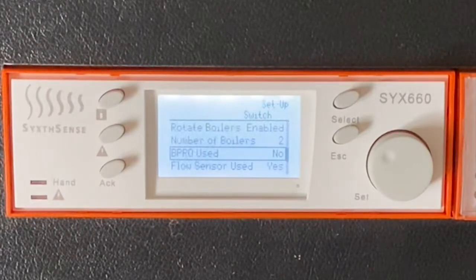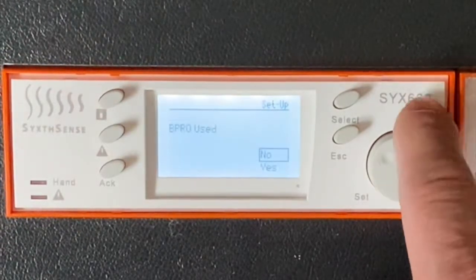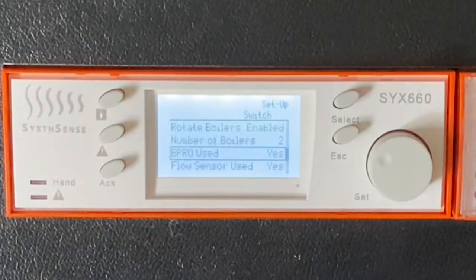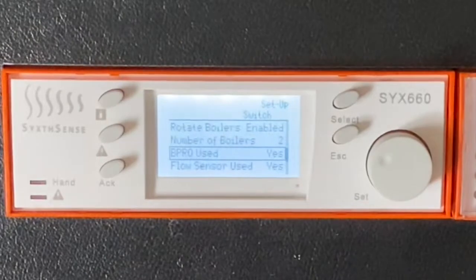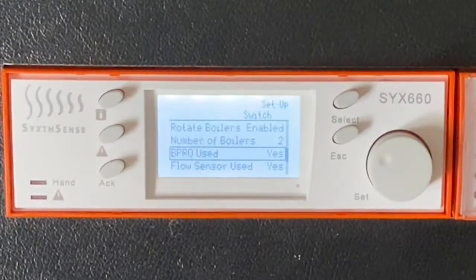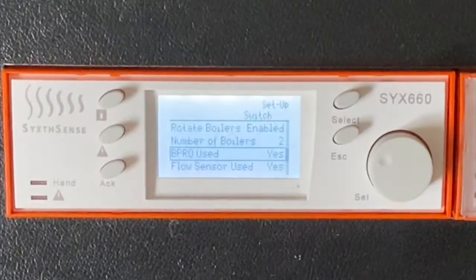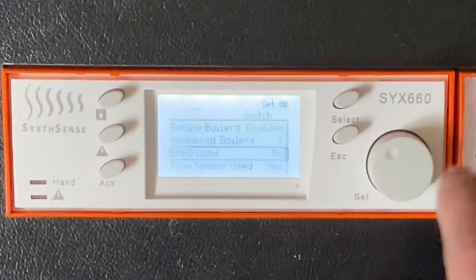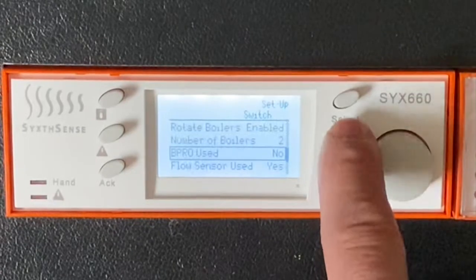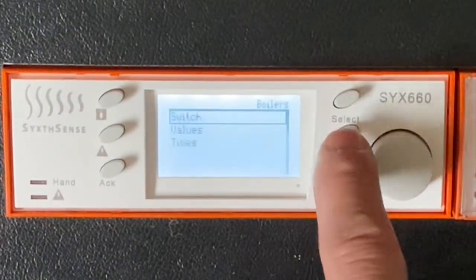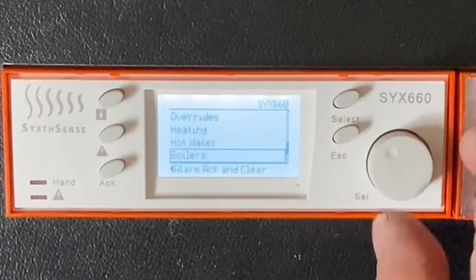So that will allow us to send a 0 to 10 volt signal to the Boiler Pro, and we have to select this option here to yes, so that we end up with the correct scaling of the 0 to 10 volt output to match that to a Boiler Pro. Okay. If you don't have a Boiler Pro selected, or you don't use a Boiler Pro, it won't matter whether that's set to yes or no, so you can just leave it as default. Okay, so that's the boiler setup. Press escape, escape, and back to the list again.